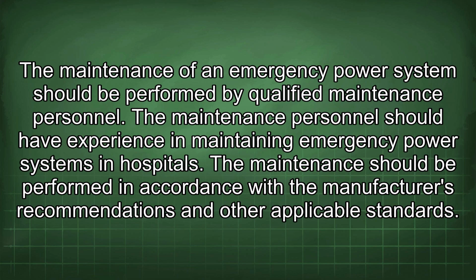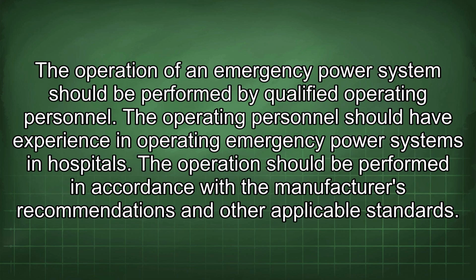The maintenance of an emergency power system should be performed by qualified maintenance personnel. The maintenance personnel should have experience in maintaining emergency power systems in hospitals. The maintenance should be performed in accordance with the manufacturer's recommendations and other applicable standards. The operation of an emergency power system should be performed by qualified operating personnel. The operating personnel should have experience in operating emergency power systems in hospitals. The operation should be performed in accordance with the manufacturer's recommendations and other applicable standards.